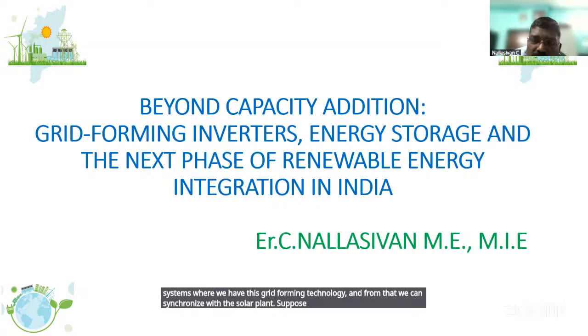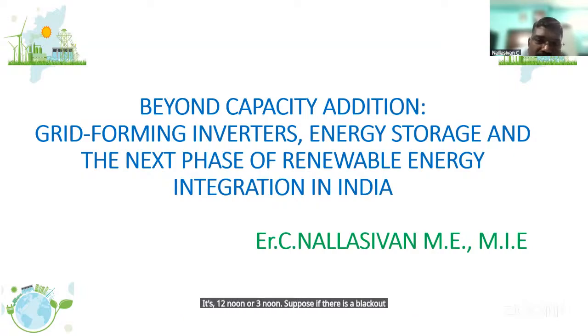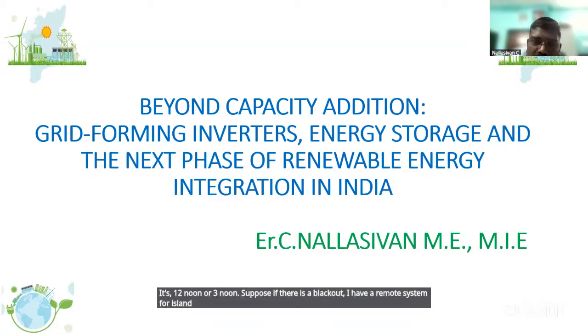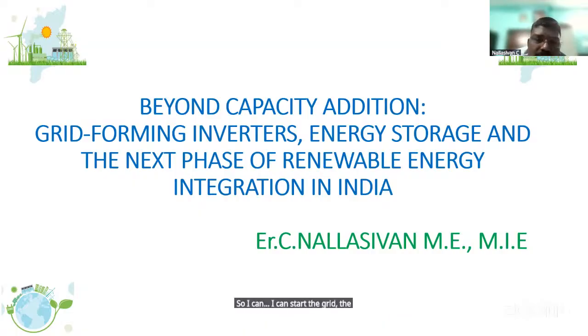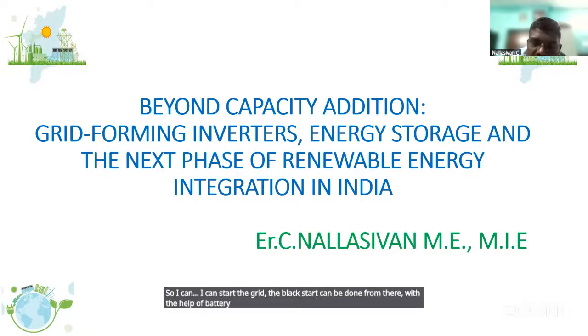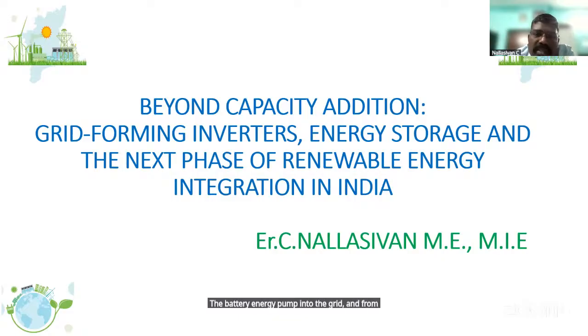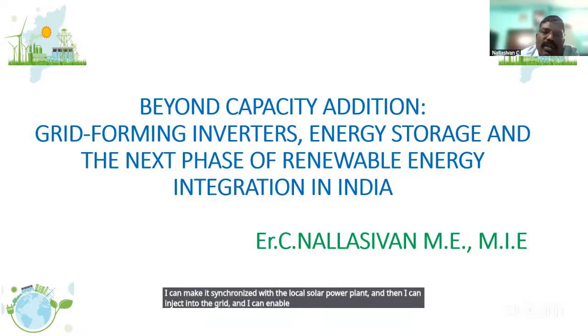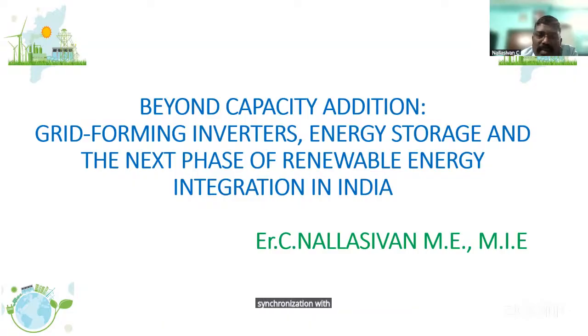Suppose it's 12 noon or 3 pm, and there is a blackout. I have a remote islanding system somewhere down in Ramnad or Sivaganga district. So I can start the grid, the black start can be done from there with the help of battery energy storage systems where there is a grid forming inverter. I can make the battery energy pump into the grid, and from that synchronize the isolated systems. I can initially island it, make it synchronize with the local solar power plant, and then inject into the grid, enabling subsequent synchronization with whatever available mechanisms to bring it back into the grid.